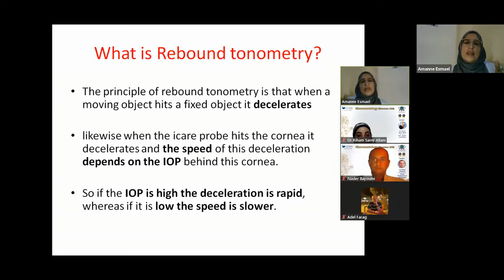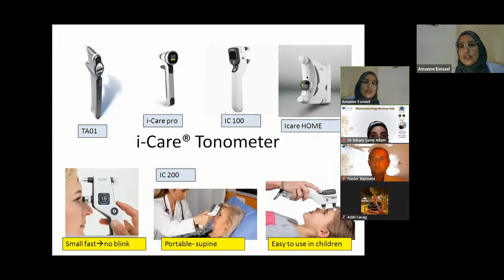The first device produced by iCare was the TA01. However, there's an array of devices with different advantages in correlation to each other. So how does it work? You have a stainless steel wire that is held in place through an electromagnetic field. This wire ends in a plastic segment that ends in a small ball that has a diameter of 1.8 millimeters.